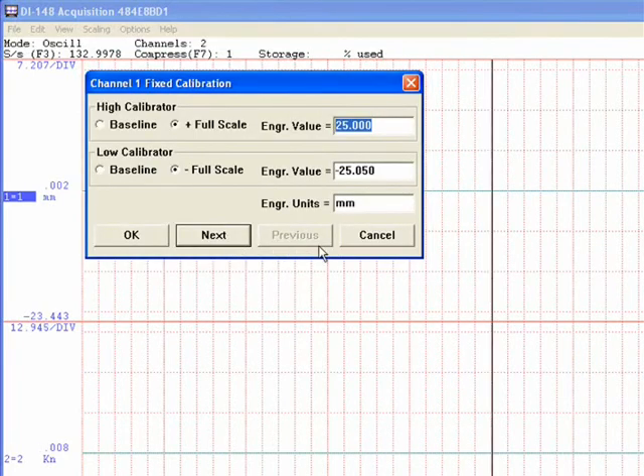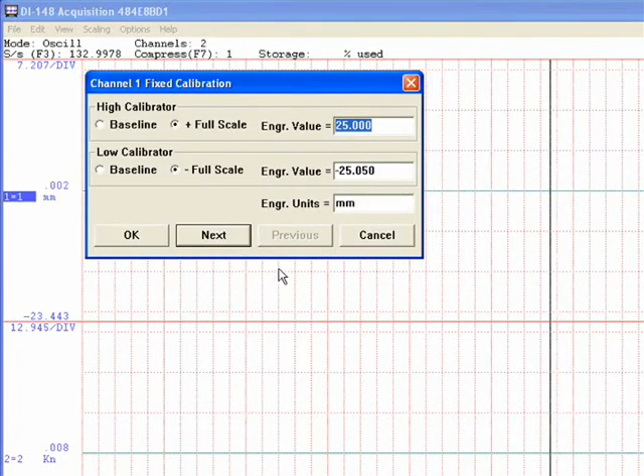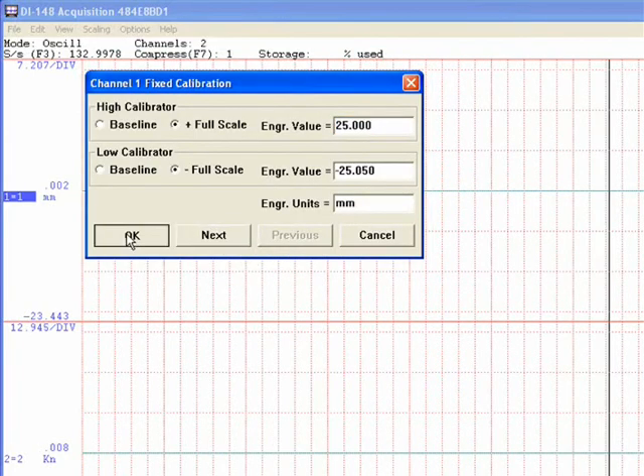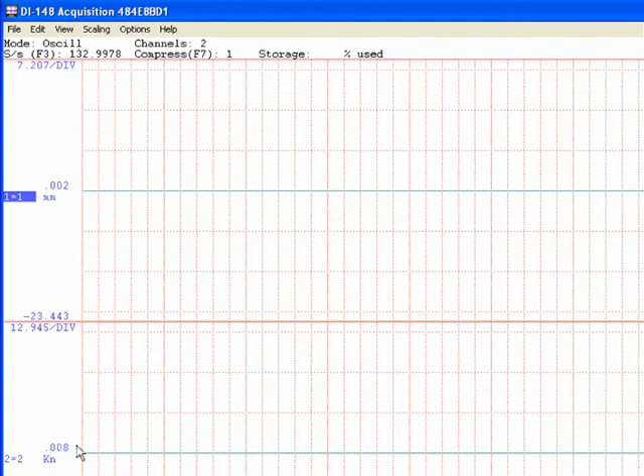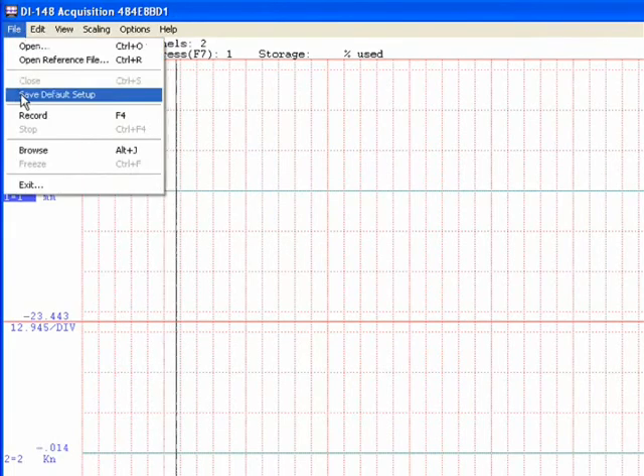And there we go. That is close enough. Say OK here. And now you have set both your zero points. File, Save Default.